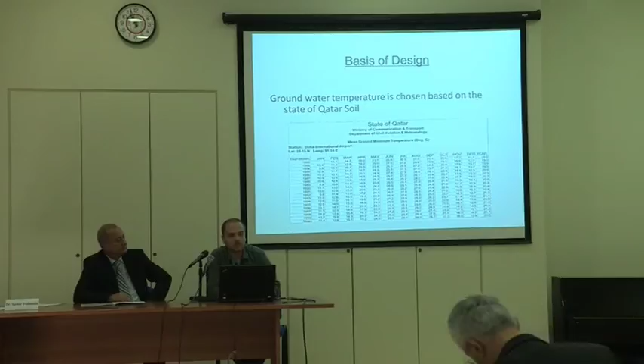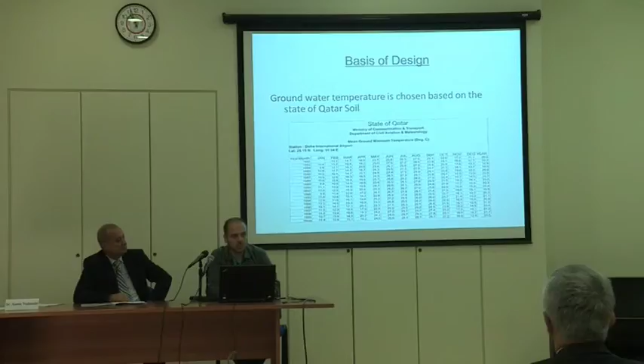The targeted energy to be dissipated within the ground is 1400 kilowatts. We start by investigating the deep soil temperature. We checked published data by the state of Qatar, and the deep soil temperature tends to be around 26 degrees, close to the yearly average temperature at that location. The two options that we investigated are the ground vertical closed loop option, which is option 1, and the second option is the groundwater open loop.